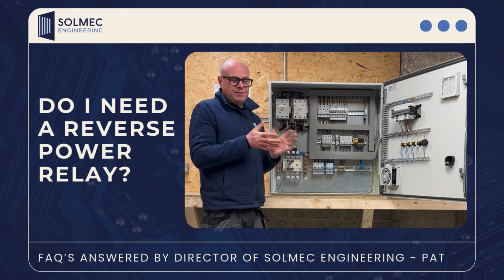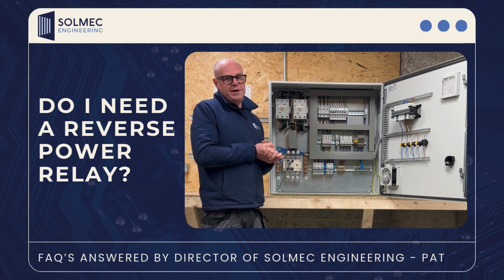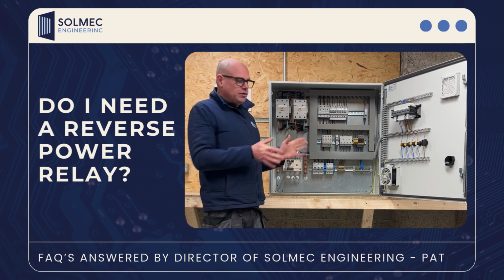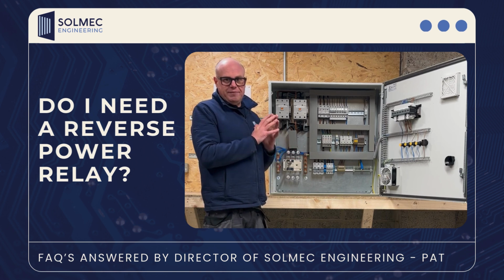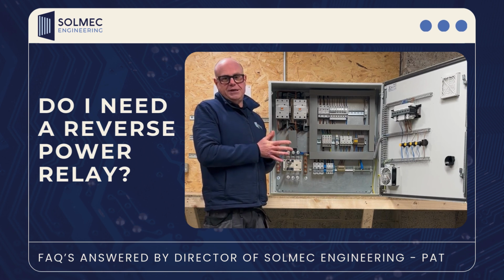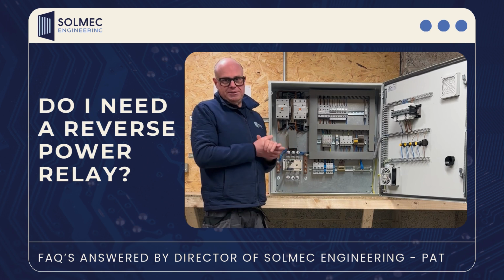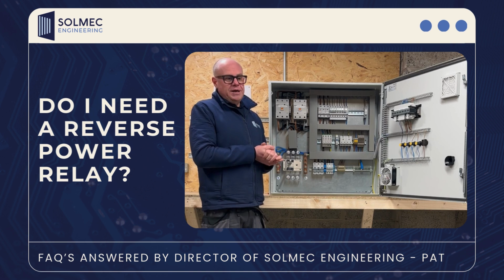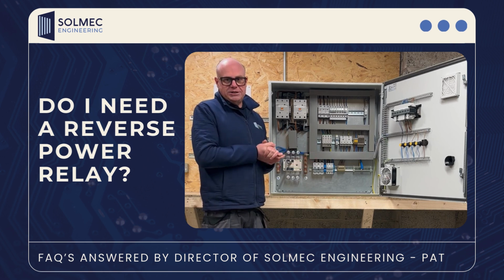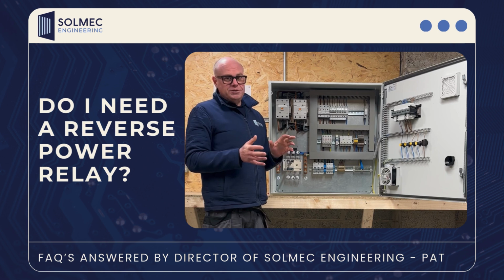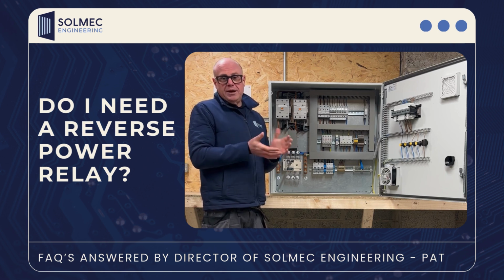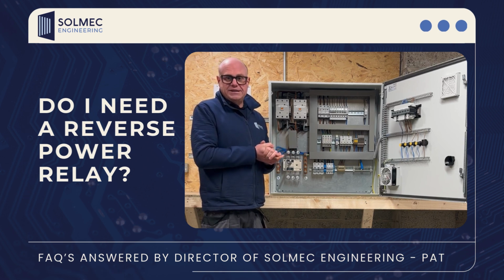A lot of questions come in, a lot of people say, oh, I need one with a reverse power relay. Believe me, you don't. I've done hundreds of these witness tests and I have a very good relationship with the guy in the ESB. We've asked him all these questions before, we've done all the tests before, and I have hundreds of these passed. You do not need a reverse power relay in small scale generation, unless you're using some sort of inverter which wouldn't be allowed anyway because you have to send it off on your NC6 application.